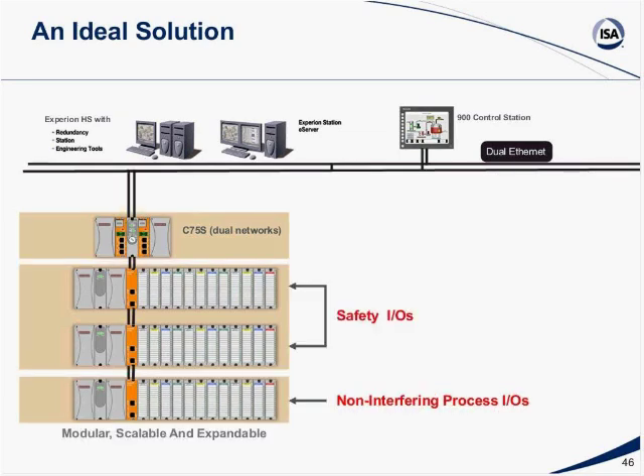When you look at this diagram, it shows the advanced capability of the system, where our HC 900 system allows safety IOs and non-safety IOs within the same architecture. There is provision within the software for a process worksheet and a safety worksheet too. Programming is possible depending on your application needs, and the process information is totally non-interfering with safety data. There is no exchange of information between process and safety because it's totally restricted.